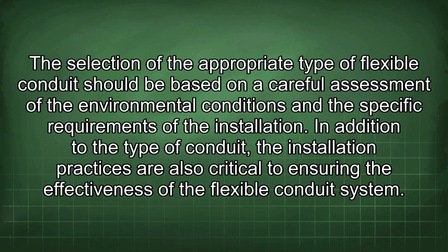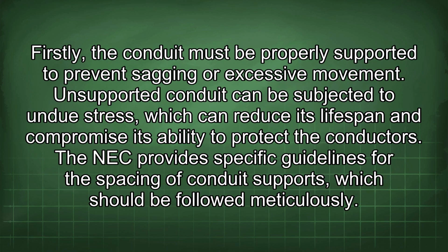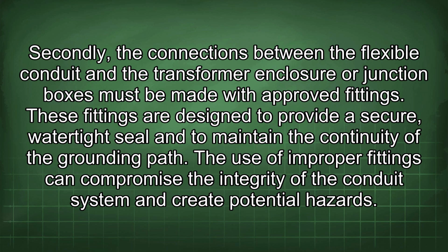In addition to the type of conduit, the installation practices are also critical to ensuring the effectiveness of the flexible conduit system. Firstly, the conduit must be properly supported to prevent sagging or excessive movement. Unsupported conduit can be subjected to undue stress, which can reduce its lifespan and compromise its ability to protect the conductors. The NEC provides specific guidelines for the spacing of conduit supports, which should be followed meticulously. Secondly, the connections between the flexible conduit and the transformer enclosure or junction boxes must be made with approved fittings. These fittings are designed to provide a secure, watertight seal and to maintain the continuity of the grounding path. The use of improper fittings can compromise the integrity of the conduit system and create potential hazards.